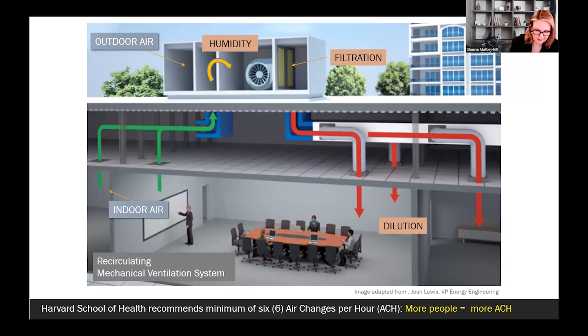Before the air is recirculated in these systems, it goes through a machine which filters the air, humidifies it, cools or heats it, and then throws it back into the space. And you can see this happening on the right-hand side. Then the indoor air is exhausted and recirculated back through this system. Most systems are designed to provide somewhere between 3 and 4 complete air changes per hour. But the Harvard School of Public Health, since the pandemic, has been studying the best air changes and recommends up to 6 air changes per hour.